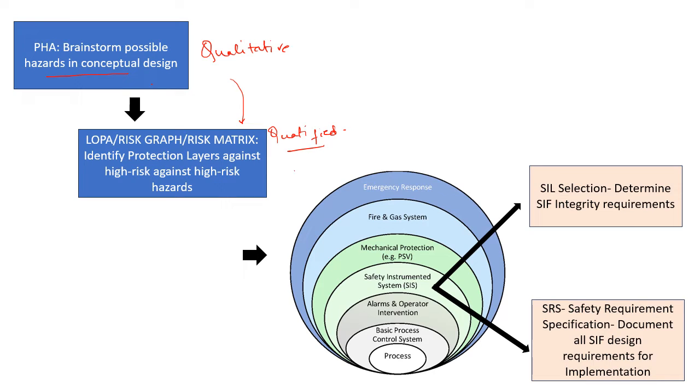This is what is generated out of LOPA, this onion ring. So you have your process, your basic process control system, your alarm, and then you have emergency, fire, mechanical protection, everything is there. In between what is left is your safety instrumented system. During the LOPA all these layers are identified, and how much risk reduction is possible by each of this layer is also being calculated.